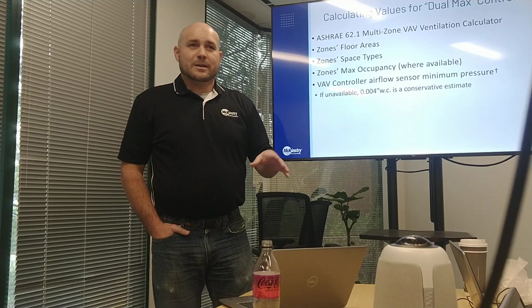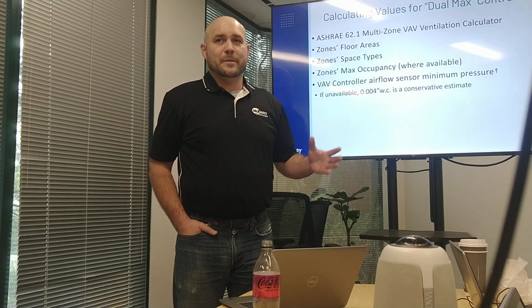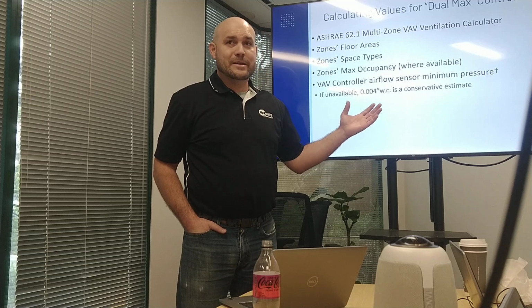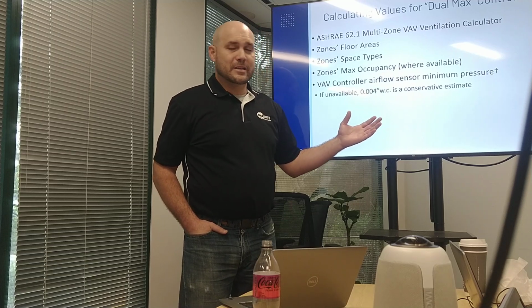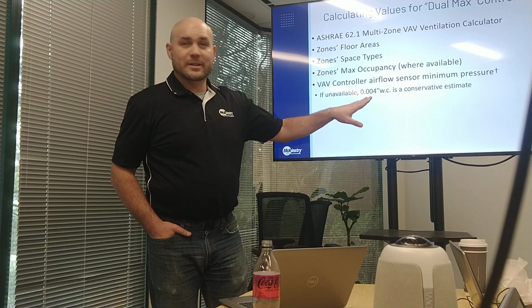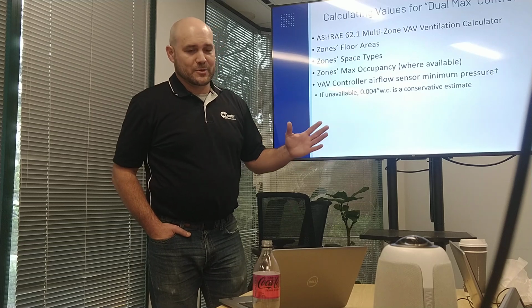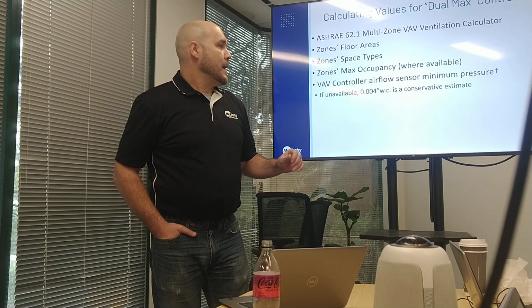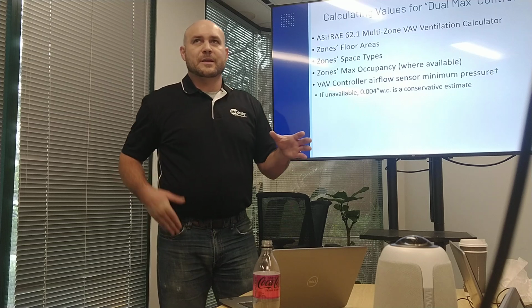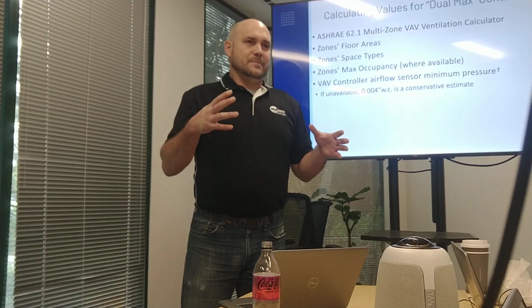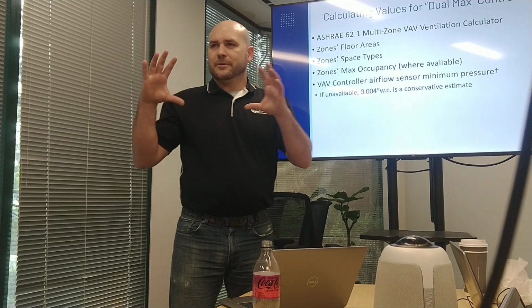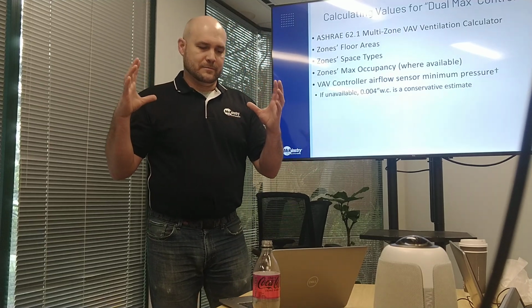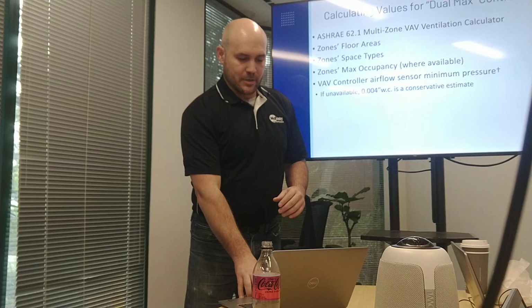Depending on the vintage of the box, if the box is 20 years old, maybe you only want to go to 0.008. But in any case, even old boxes are at least this sensitive. It's just a matter of how conservative we want to be. VAV boxes measure air speed, and then you multiply it by the cross-sectional area of the duct, and that gives you the airflow.